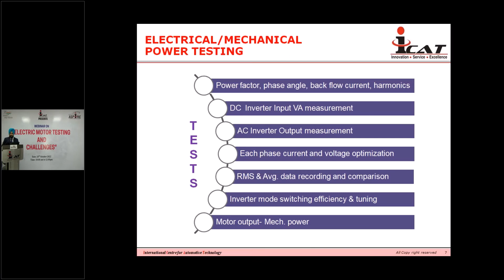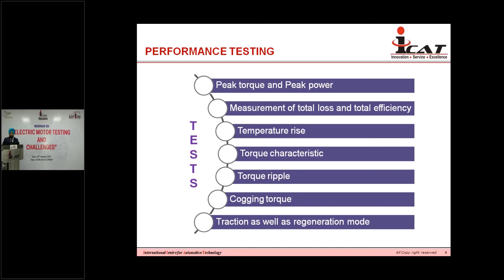Under performance testing, the tests include peak torque and peak power measurement, total loss and total efficiency, temperature rise, torque characteristics, torque ripple, and cogging torque. All of these tests are also covered in the IS standards.